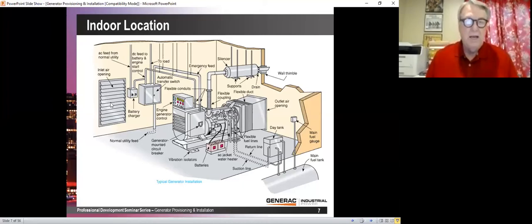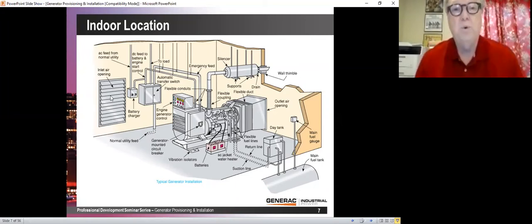Now, how about this inlet air opening? Is that large enough? Well, right here is the radiator, and you can see the radiator comes through the flex duct, and then the sheet metal flares out to the louvers, and the air exhausts outside the building. I like that. That all looks great, exactly how it should be. Now, take a look at the size of the radiator, and the inlet air opening should be 1.5 to 2 times. I would like to say 2 times the size of the radiator, and that should be the clear square foot or square inches of the inlet or opening, not the size of the inlet opening, but how much free airflow there is in there.